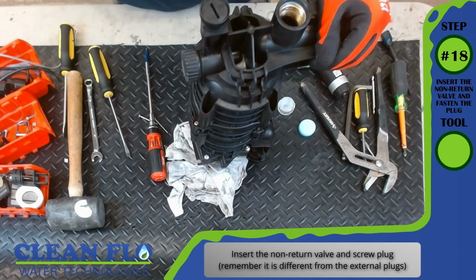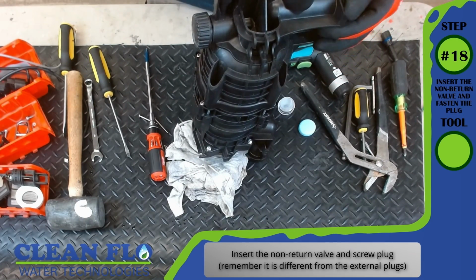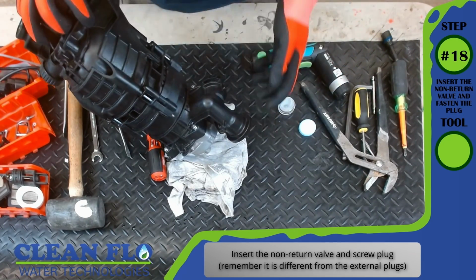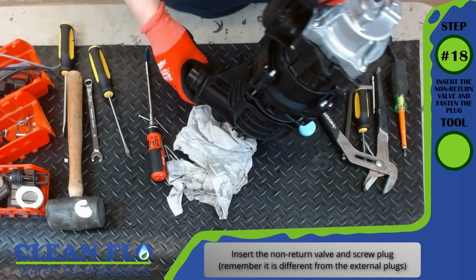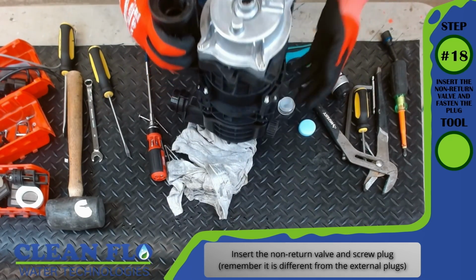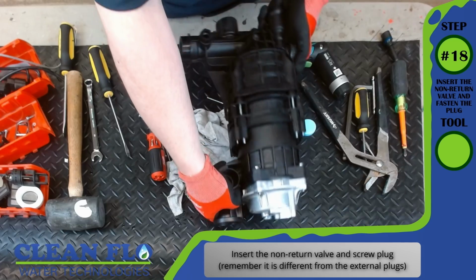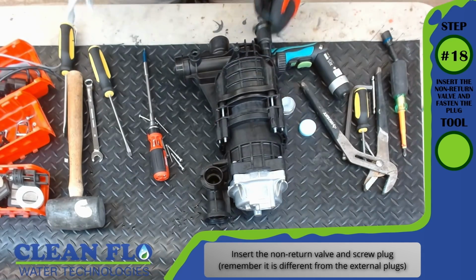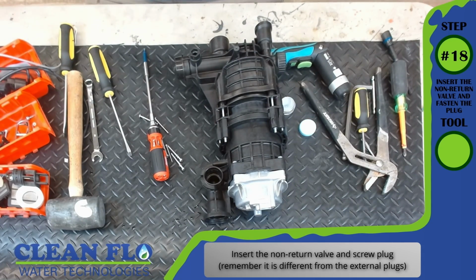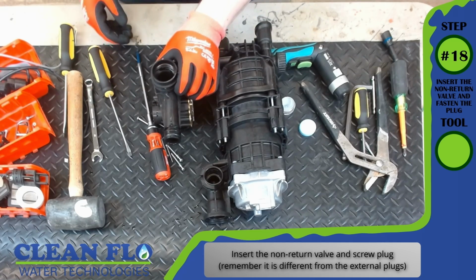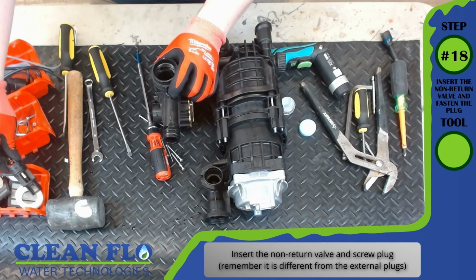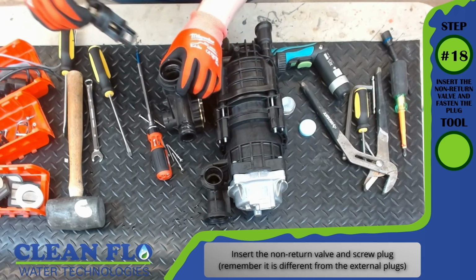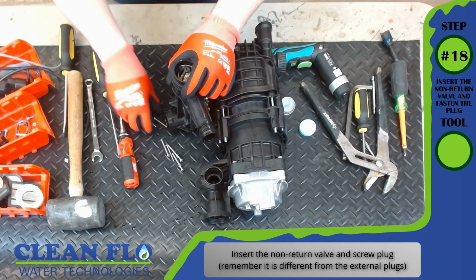Step number 18. Insert the non-return valve and fasten the plug. Insert the non-return valve and screw plug. Remember, it's different from the external plugs. Now the non-return valve sits in the secondary assembly that has the water-cooled heatsink for the VFD. The non-return valve gets pushed into place. You'll feel it click in.